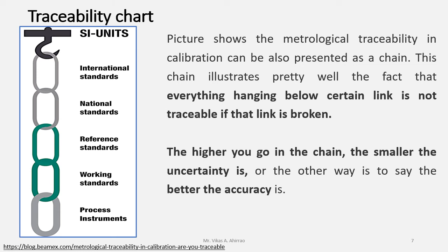In turn, the reference standards in every country will get calibrated with the national standards. For every country, national standards are at the apex level, but these standards are calibrated in comparison with the international standards, and the international standards are derived from the SI units. In this way, there will be an unbroken chain, and this chain is called the unbroken chain of comparisons. The higher you go in the chain, the smaller the uncertainty is, or the other way to say it, the better the accuracy is. Now we will go through a hypothetical example to understand clearly what traceability means. At the time of calibration, the unbroken chain of comparisons should be verified.